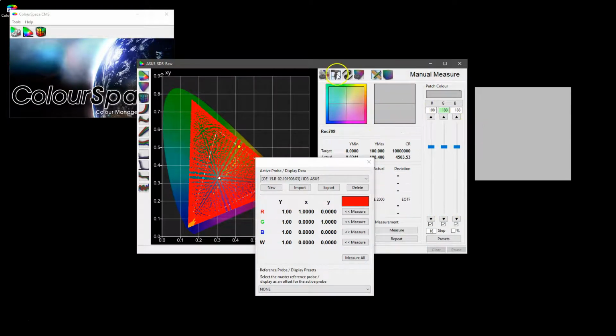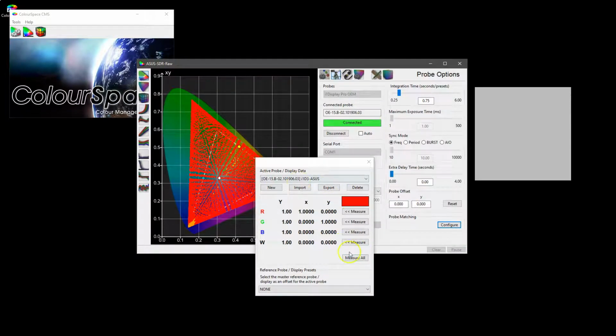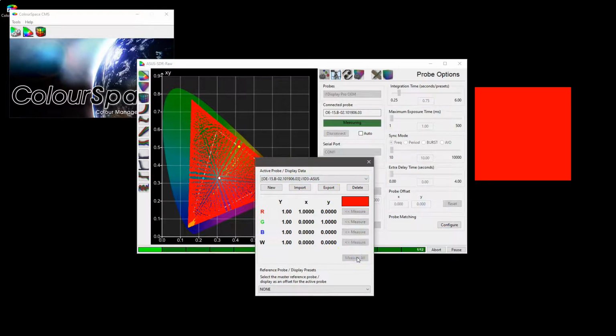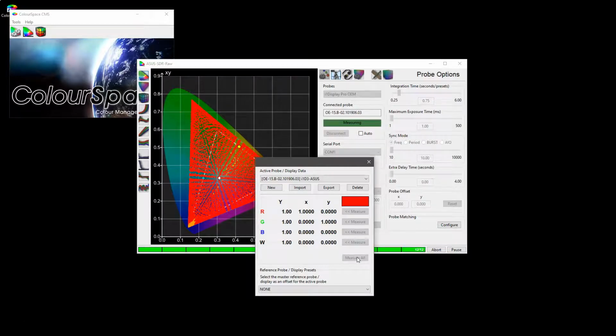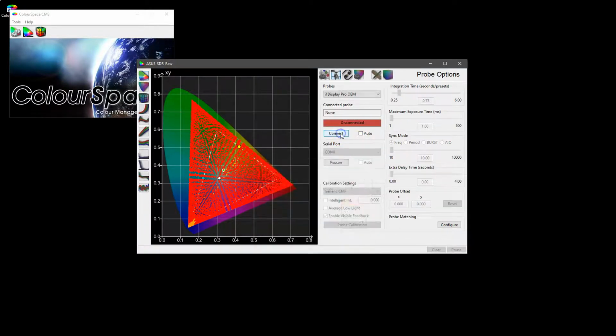The probe is on the patch, and within the active probe settings configuration, we will measure all, and it will cycle through the red, green and blue, taking 3 measurements of each, and then do white as well. Okay, so we now have the measurements for the i1D3 on the ASUS using the red, green, blue and white patches. Okay, we will now disconnect and select the i1 Pro 2 and connect to that.